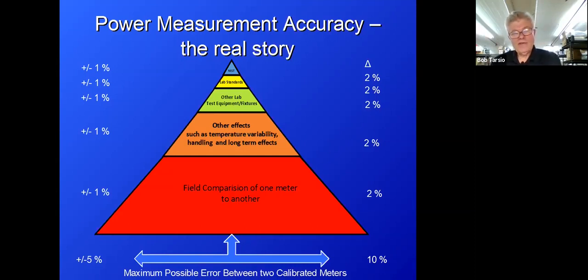So if you notice on the left-hand side of this presentation, this slide anyway, we're stacking up differential errors. So we've visited NIST, we've been to Gaithersburg and back, and we know that we now have a plus or minus 1% error is the closest that we're going to get to a traceable standard. While the laboratory standards that we use and other companies use, and they may vary in which type that they use, is the next rung of the triangular ladder here. That's the yellow, the lab standards.